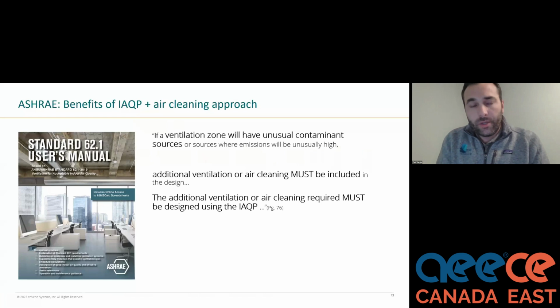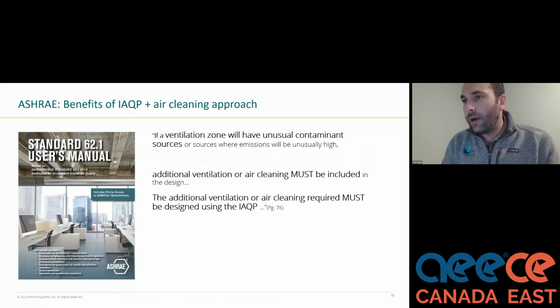Moving on here, what are some of the benefits? Well, the benefits of the indoor air quality procedure and the air cleaning approach, there's many. But the new ASHRAE 62.1 Users Manual for 2019, which was recently published, basically says that the IAQP is a better methodology in several situations or may be more appropriate to use. And one of those situations is if the ventilation zone has unusual contaminant sources, then additional ventilation or air cleaning must be included in the design. And that additional ventilation or air cleaning required must be designed using the IAQP. This is very interesting, right? This is a massive pivot.